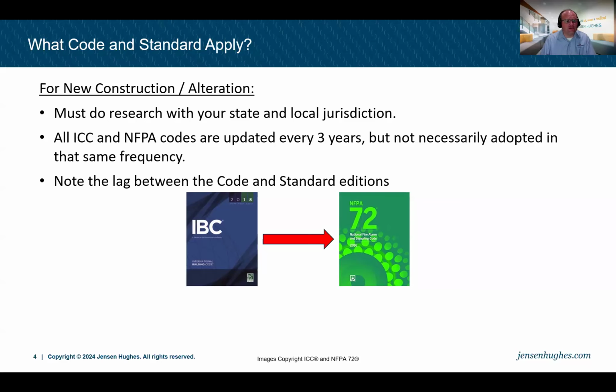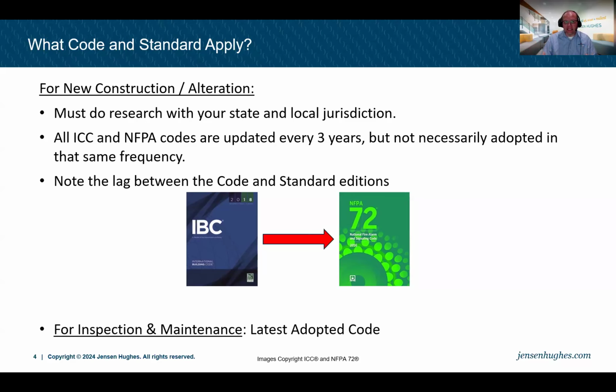Now, since all codes and standards are always being adopted, how do we keep track of all this? Well, there is something we need to know, because we said this applies to new construction or alteration, like a tenant finish and whatnot. But for inspection and maintenance, it's the latest adopted code in your jurisdiction. And that's important to note, because as soon as an installation standard like NFPA 72 is adopted in your jurisdiction, that becomes the rules for inspection, testing, and maintenance that you need to follow. So it's important to keep those kinds of things in mind.